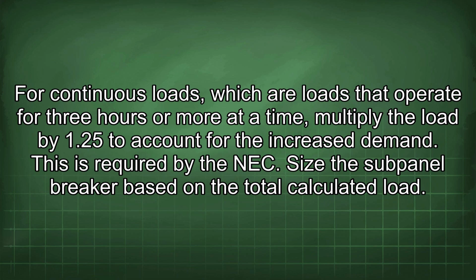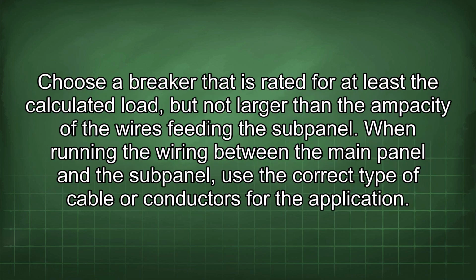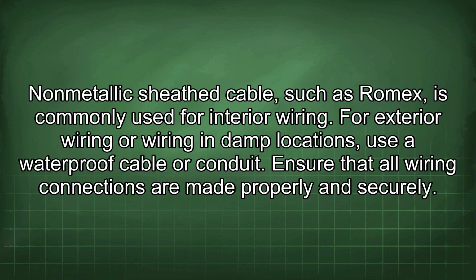Size the subpanel breaker based on the total calculated load. Choose a breaker that is rated for at least the calculated load, but not larger than the ampacity of the wires feeding the subpanel. When running the wiring between the main panel and the subpanel, use the correct type of cable or conductors for the application. Non-metallic sheathed cable, such as Romex, is commonly used for interior wiring. For exterior wiring or wiring in damp locations, use a waterproof cable or conduit.